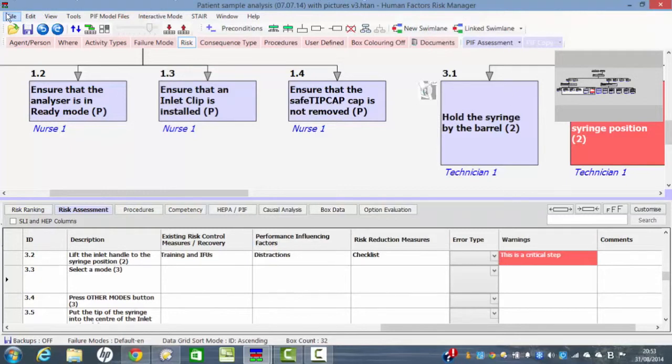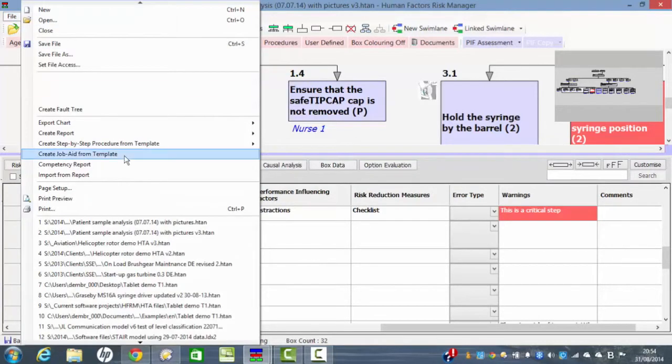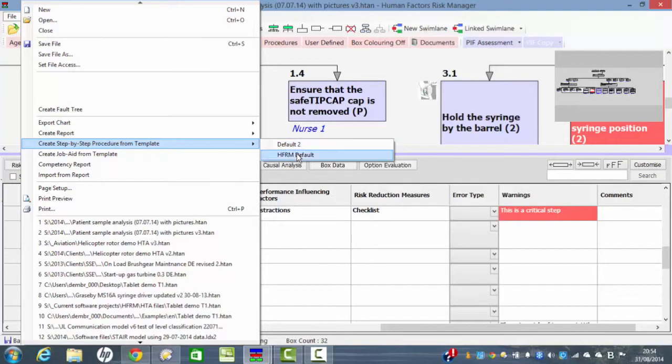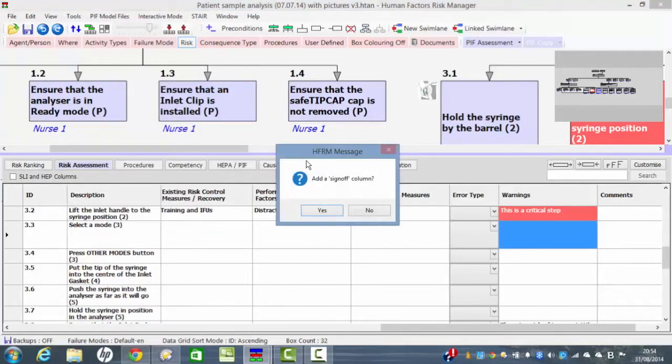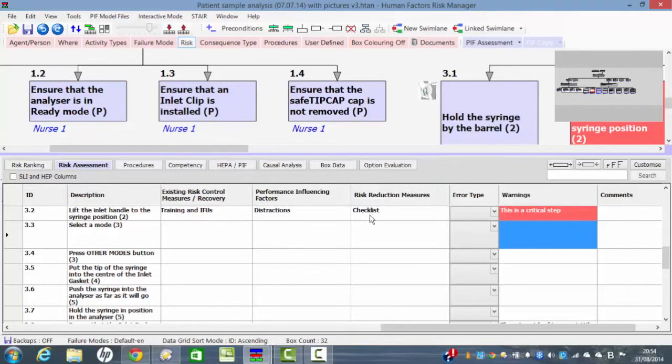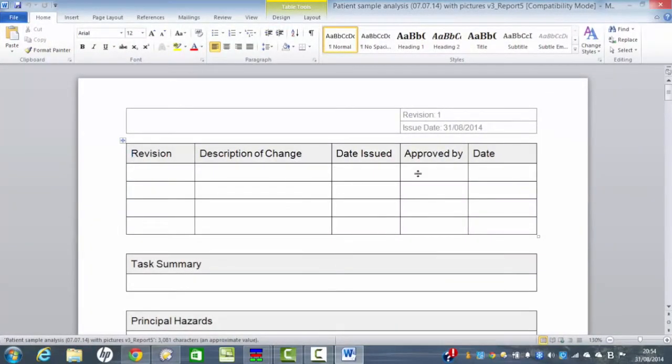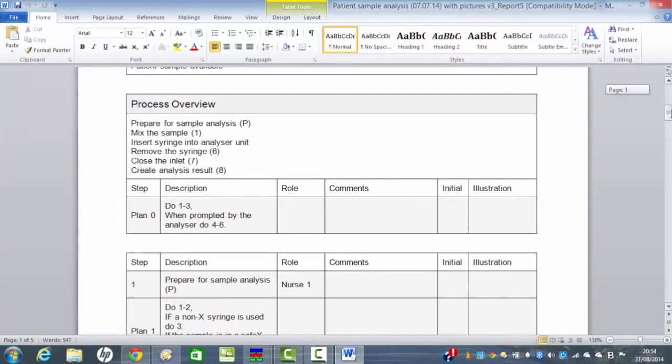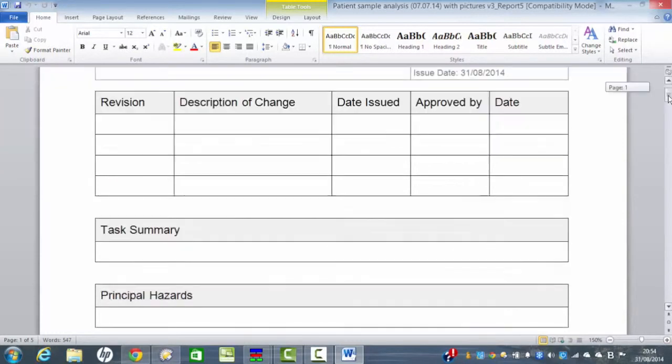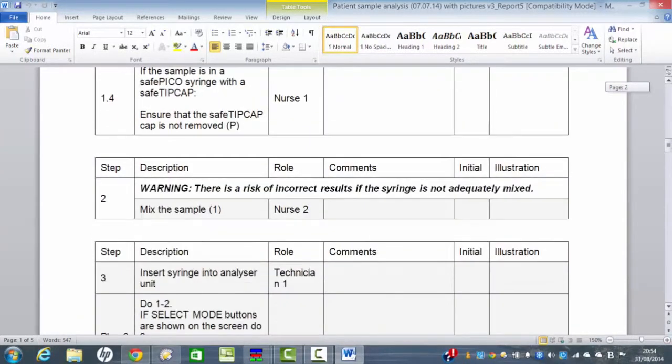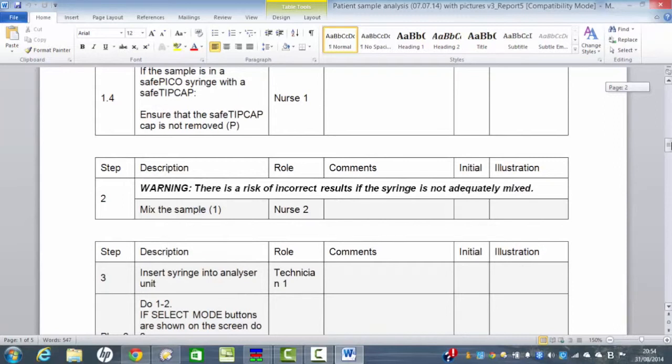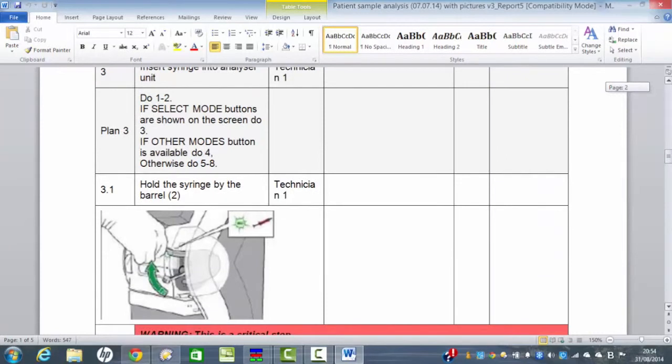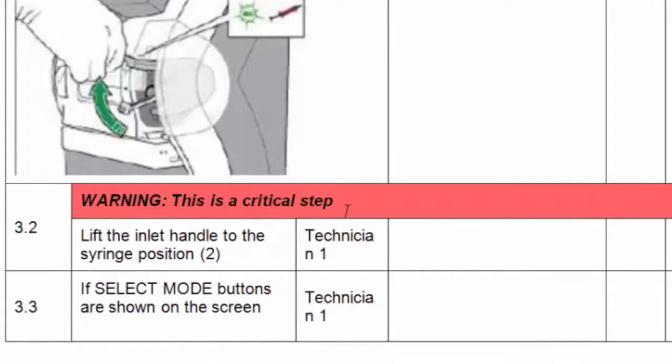So we've now carried out a risk analysis which is captured in this risk assessment document. If we now create a procedure from that risk analysis or an IFU from that risk analysis or a training regime this can be done automatically by this process and so you'll then see that when that's been done the software automatically opens a word version of the new procedure. So here is the overall subtasks that have to be carried out. Here are the separate description of these subtasks and warnings which are embedded in the text. Here are some photographs which have been embedded in the procedure when these are taken from the files that we've captured during the analysis process and you'll see that this new step that we've just inserted there saying this is a critical step is also captured.